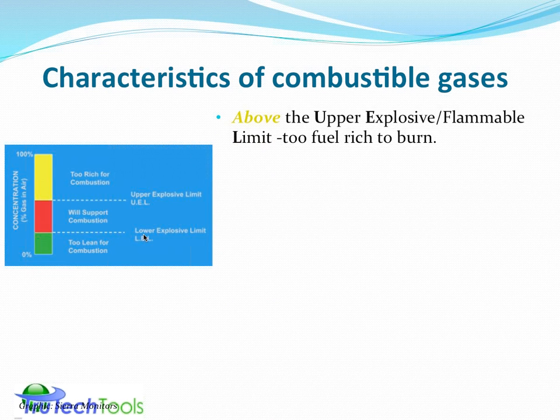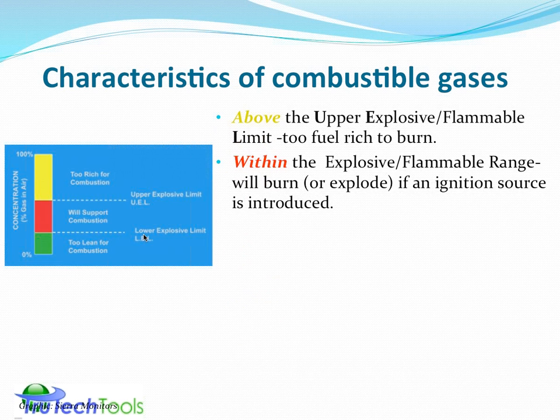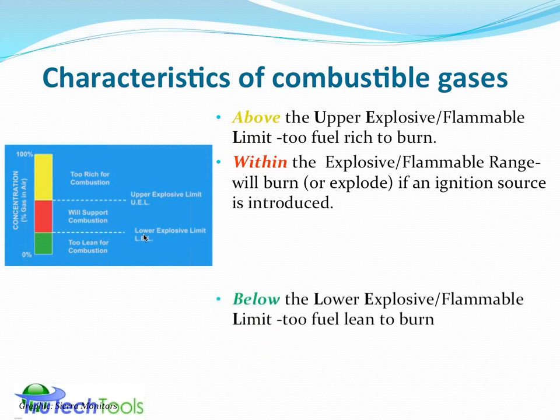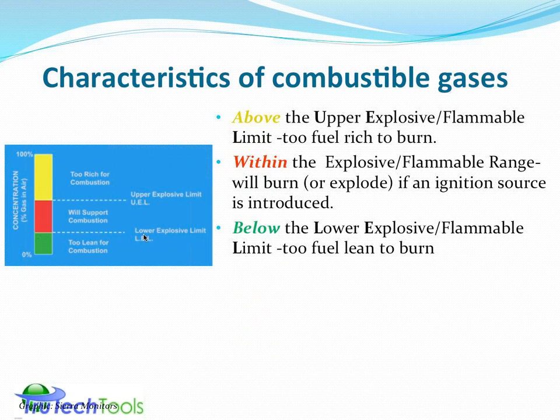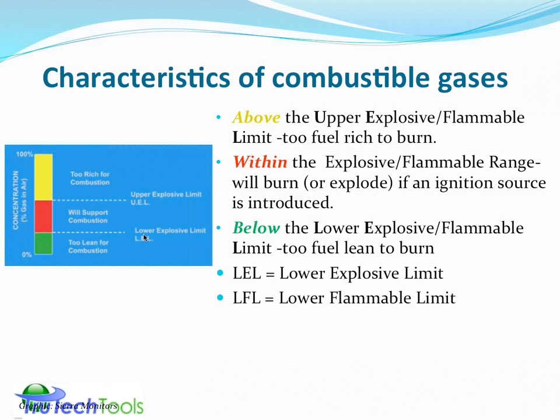It's also sometimes called the upper flammable limit, or the UFL. That's an area above which it's too fuel rich. The concentration of the fuel gas in the air is too fuel rich to burn. Not enough oxygen around. Within that range, the red area, it could burn or explode if an ignition source is introduced. And then below the lower explosive limit, or the lower flammable limit, it's too lean on fuel to burn. There's more oxygen available, and there's not enough fuel available for combustion to light off.